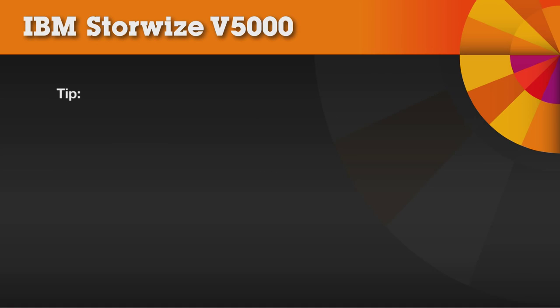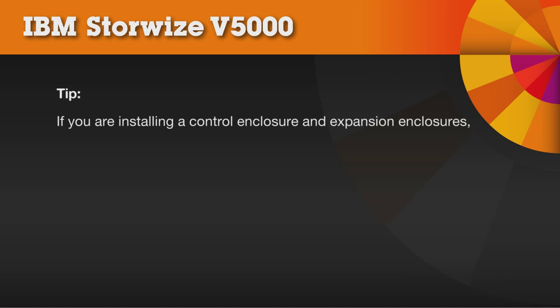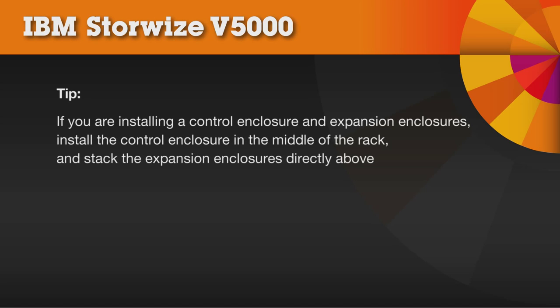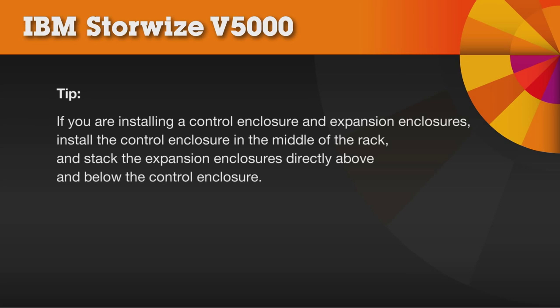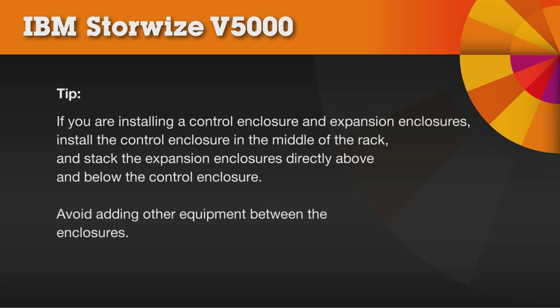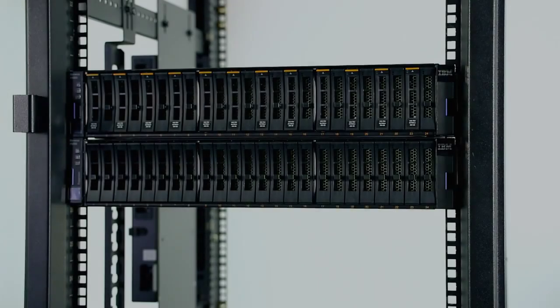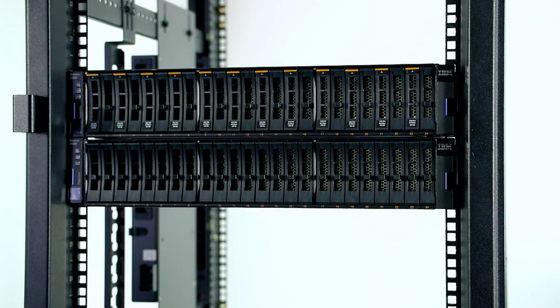Here's another tip. If you are installing a control enclosure and expansion enclosures, install the control enclosure in the middle of the rack and stack the expansion enclosures directly above and below the control enclosure. Avoid adding other equipment between the enclosures. This helps with rack stability and serviceability. Each enclosure is two bays high.